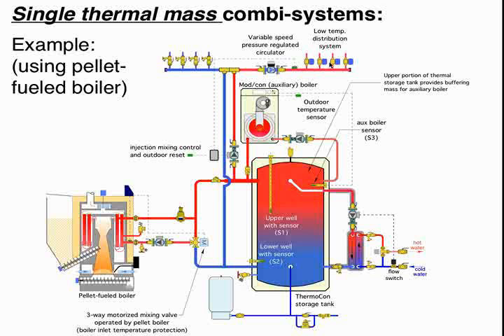Anytime we see a lot of zoning going on, we want to think about buffering, because the finer we divide up that distribution system into zones, the more likely it is that we could have a single small zone that is substantially less heat demand compared to what our heat source is capable of delivering. Even a ModCon boiler has limitations. If one zone here was 2,000 BTU per hour and ModCon can only go down to 10, that still means that the ModCon is producing heat 5 times faster than the load is requiring.